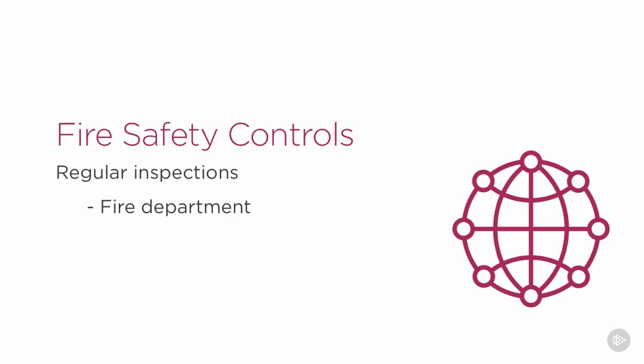The other thing about the fire department is it helps if they are familiar with our building. If I have a UPS system, for example, in the telephone industry, we often have a room full of batteries, large lead acid batteries that are all huge, hundreds of pounds apiece. And the last thing you want a fire department doing is, if there's a fire, to walk into that room with all those batteries and maybe it's smoke filled and they can't see what's in there. If they walk in there and they turn on their hoses, you're going to have a very serious catastrophe very quickly. So it's good for the fire department to be aware of some of those risks as well.